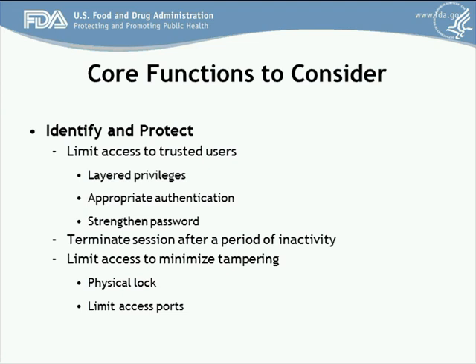The agency recommends that medical device manufacturers provide justifications in their pre-market submission for the security functions chosen for the medical device. Examples of security functions manufacturers may choose to consider include limiting access to the device through authentication of users, terminating sessions after a set period of time where it's appropriate for that use environment, using a layered authentication model, using appropriate authentications, strengthening password protection, taking steps to minimize tampering, and requiring authentication before permitting updates.